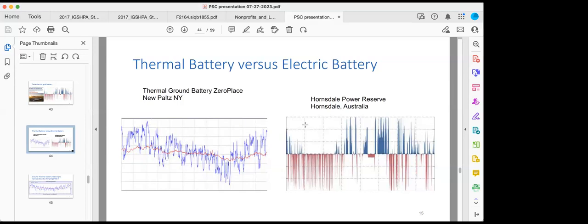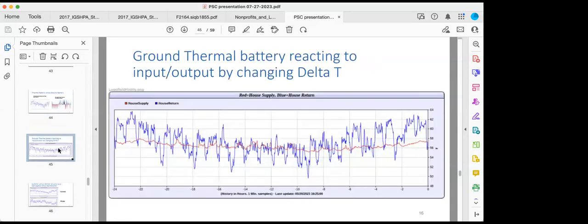How is that different from a large-scale battery on the electric side? My point is the loop field behaves exactly like a battery, it just stores thermal energy instead of electricity. It reacts directly to input and output, there's no other way to discharge the thermal energy than putting it into the loop field, and then you get it back out. There's no other source for it, except of course the electrical draw for the compressors.